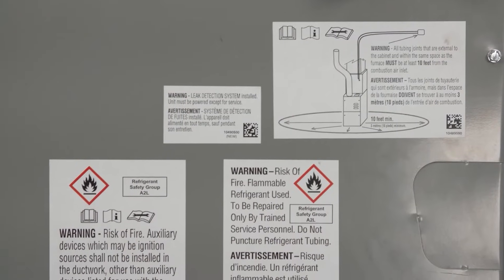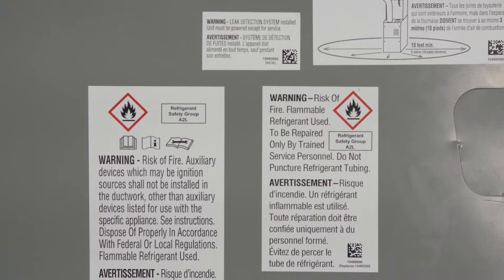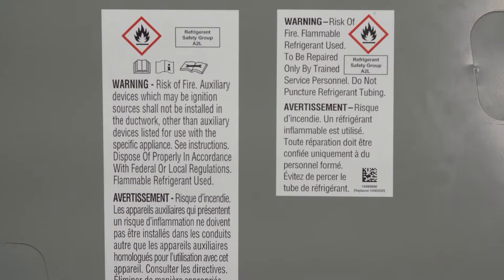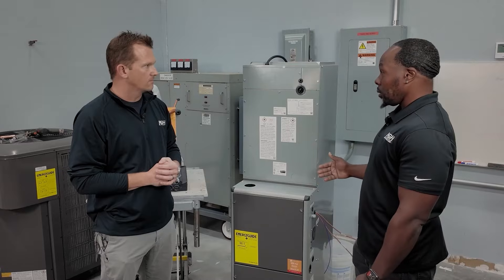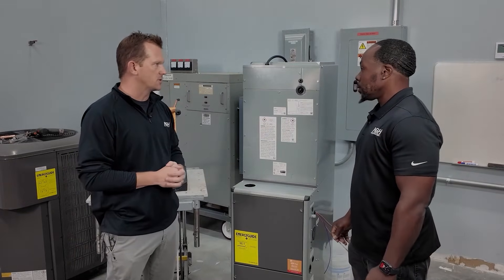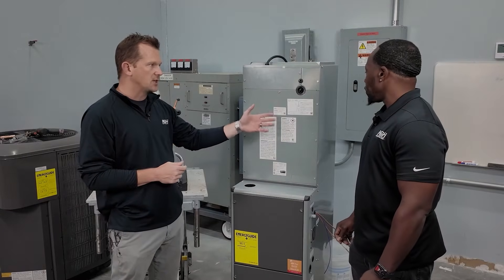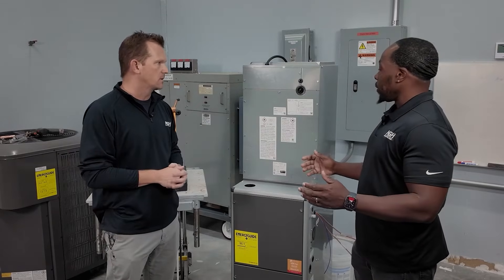These are labels that you will find for anything that is going to be R454B, just to let you know about the flammability and the risk. You also find here another label that tells you where to make connections in the event that you need to make one outside of the coil cabinet. That 10-foot number — we're advising that the braze connection be at least 10 feet away from the ignition source.